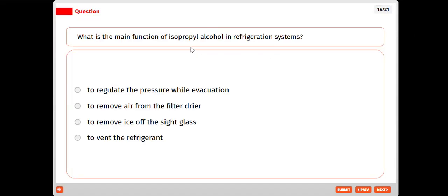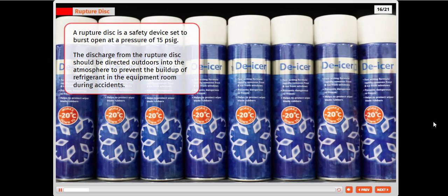What is the main function of isopropyl alcohol in refrigerant system? To regulate pressure while evacuation, to remove air from the filter dryer, to remove ice off the sight glass. A rupture disc is a safety device set to burst open at a pressure of 15 psig. The discharge from the rupture disc should be directed outdoors into the atmosphere to prevent the buildup of refrigerant in the equipment room during accidents.